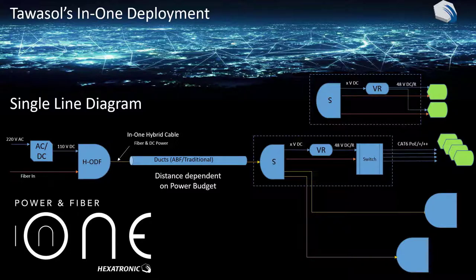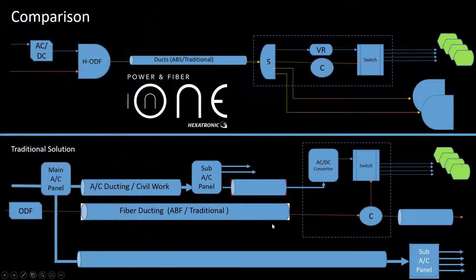The box on top is an illustration. If you have devices, there are some RF antennas that do not need Ethernet, so you can use this solution without the Ethernet switch. You just have the power voltage regulator, get the 48 volts DC out, and connect the fiber directly. If you have a camera that takes fiber directly, you don't need the switch in that case. You can take the power from the voltage regulator and feed it to your fiber camera, taking one fiber core and connecting it to the camera. So if that's your need, this is an option we have.